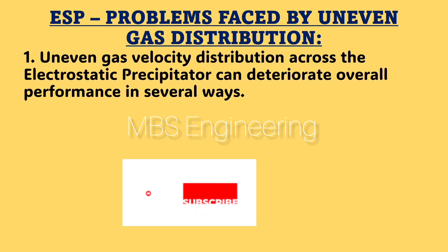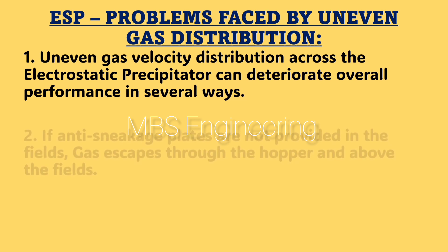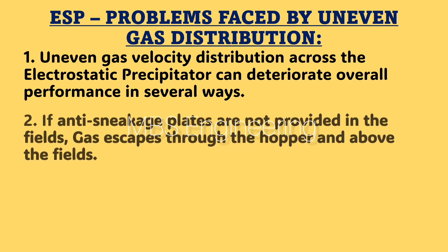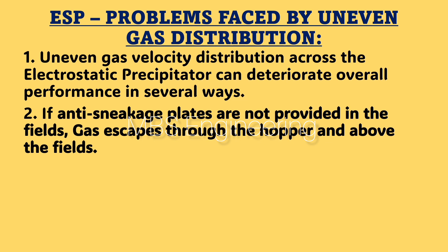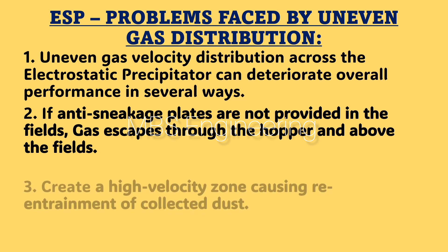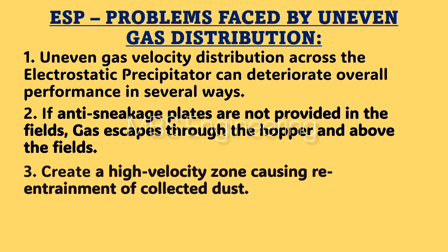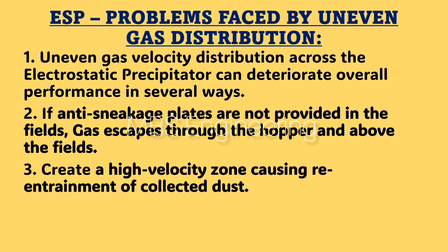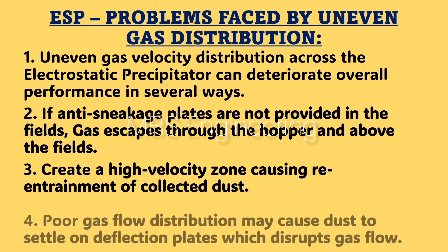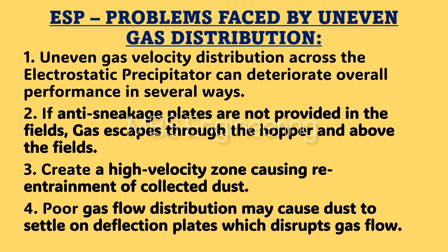Problems faced by uneven gas distribution in the ESP: Point 1: uneven gas velocity distribution across the electrostatic precipitator can deteriorate overall performance in several ways. Point 2: if anti-sneakage plates are not provided in the fields, gas escapes through the hopper and above the fields. Point 3: it creates a high velocity zone causing re-entrainment of collected dust. Point 4: poor gas flow distribution may cause dust to settle on deflection plates, which disrupts gas flow.